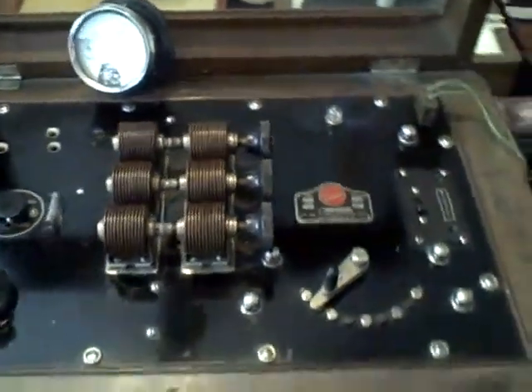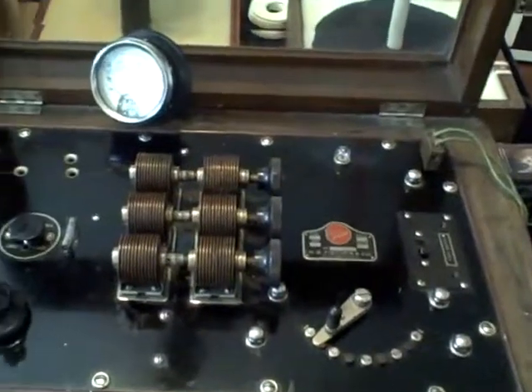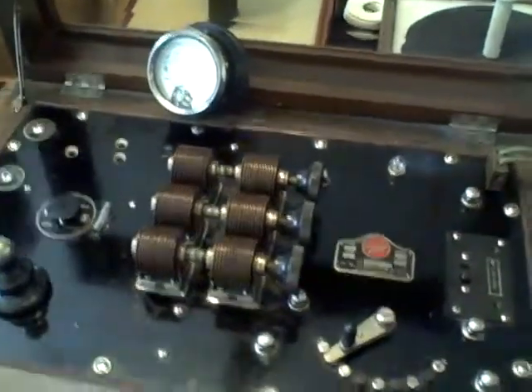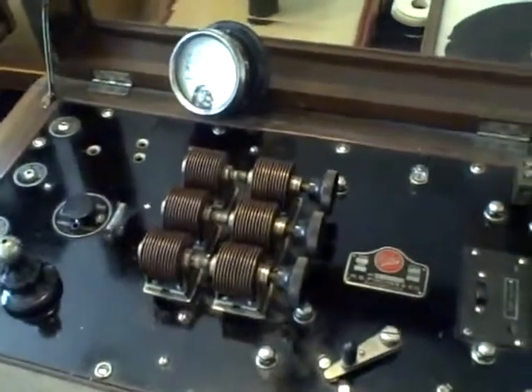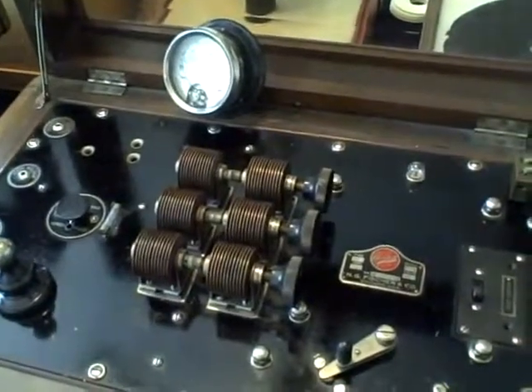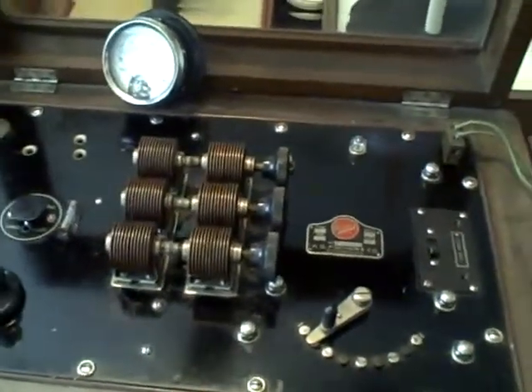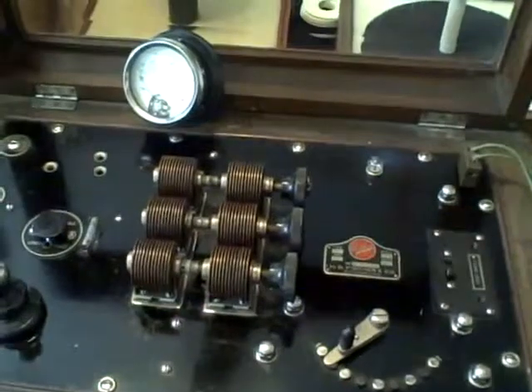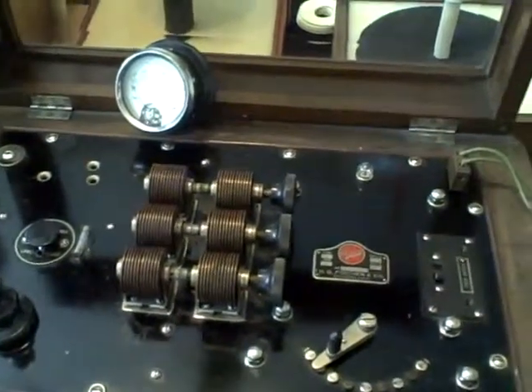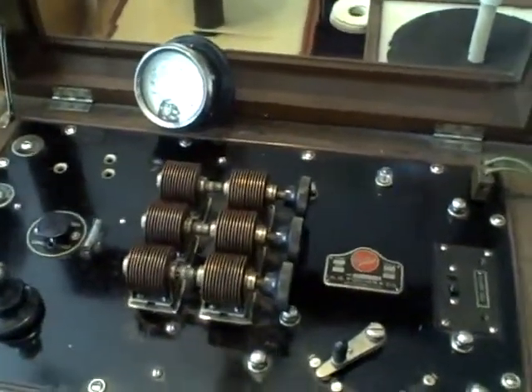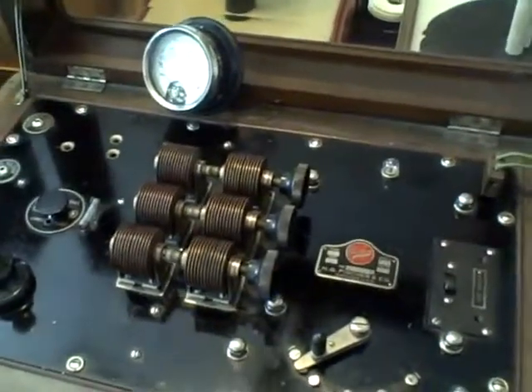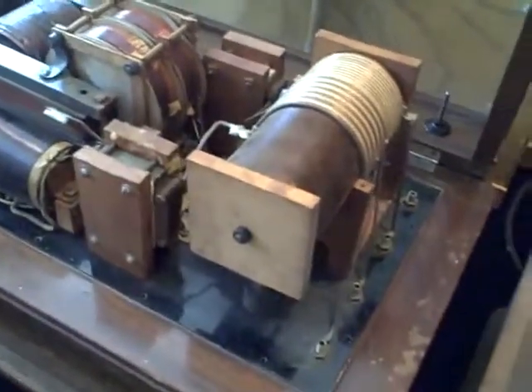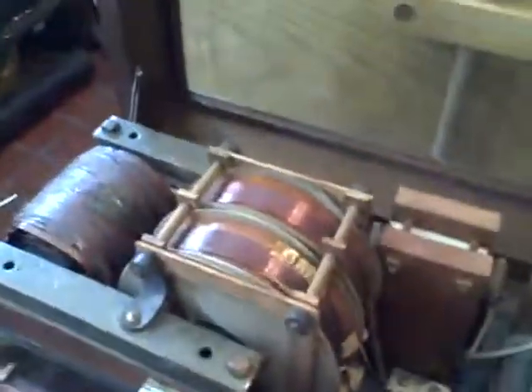But for surgical use, it's interesting to note that the spark gap type of Tesla coils are still used today. You can use solid state and tube-driven circuits, etc., to power a coil, but you can't exactly get the same degree of coagulation and cutting abilities that you can with a spark gap circuit. And it's just because of the damped oscillations versus undamped oscillations and how physiologically the tissues react to them.